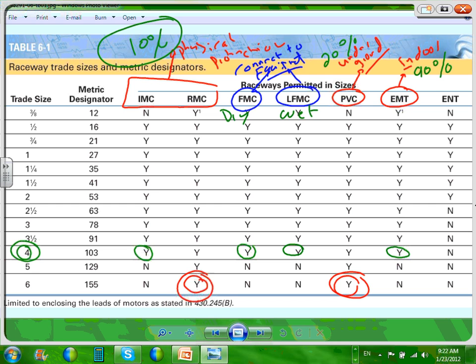The other thing I want you to look at is the sizes that you can come up with. When you do commercial design, it's not a good idea for a branch circuit to use less than 3/4 of an inch. That's my opinion. So start at 3/4 of an inch and almost always end up with this. You try to fit your design between 3/4 of an inch and a 4-inch, unless you have a bigger feeder. You can use 4, 5, and 6. Why are 5 and 6 bad? Because they're limited in the type of conduit you can use.